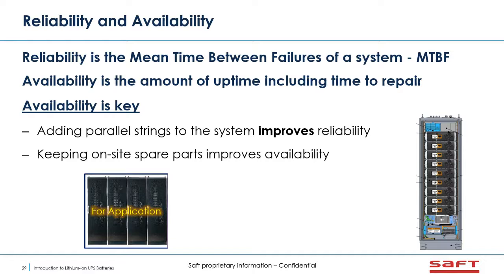Finally, reliability and availability. A few definitions here. Firstly, reliability is the mean time between failure of a system, so the MTBF, and the availability is really the amount of uptime, and that typically includes the time to repair. And we know availability is key. There's 2 key functions to add here, is that you can add parallel strings to really improve the reliability, and that's for VRLA or lithium ion. So quick kind of picture here is you can easily add an N+1 configuration, greatly improve the reliability.